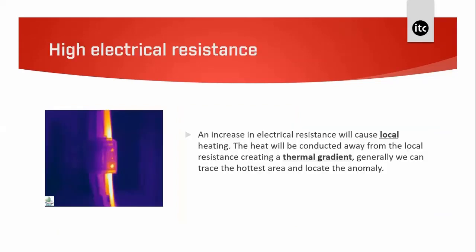Recognizing thermal gradients is key to electrical thermography. Looking at this image, we can see a connection where the cables on either side are warm near the connection but get cooler further away. Bad connections make up the majority of electrical faults detected — there is always a thermal gradient with the hottest area at the high resistance point. Note that 'high resistance' is comparative — higher than other good parts of the circuit. The connection temperature is related to electrical load, so surveys should be undertaken under normal operating conditions if possible.